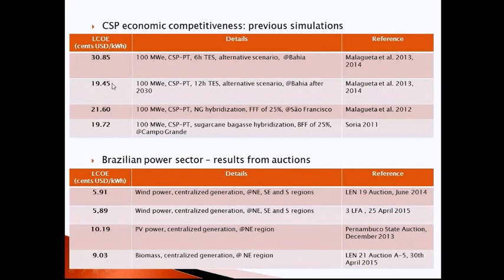In these tables, we can see that using SAM, we analyzed different configurations of CSP plants, including different sizes of thermal energy storage and different shares of backup systems to produce electricity. In all cases, the levelized cost of electricity, LCOE, was always higher than the price of electricity contracted in recent auctions, including renewable energy auctions. So we looked for an alternative to achieve cheaper electricity from CSP in Brazil.